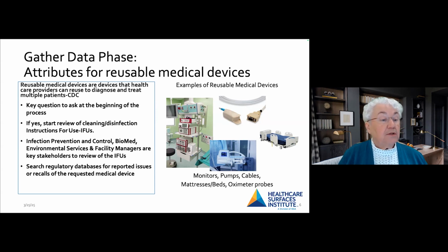If the answer is yes, then we want the cleaning and disinfection instructions for use first so we can get started on that review. We involve the variety of stakeholders you see here, from infection prevention, biomed, environmental services, facility managers, so that we're all going to get on the same page about the IFU should we select these devices. And then we're going to look for recalls and other things in databases. So these are just some examples of reusable medical devices.